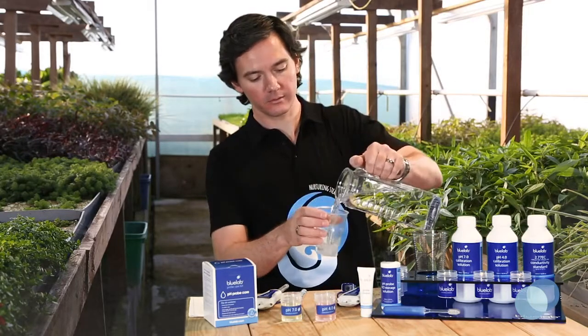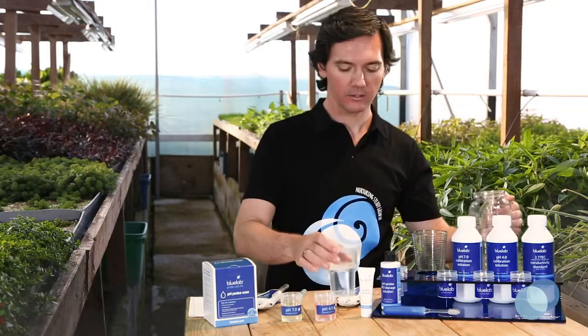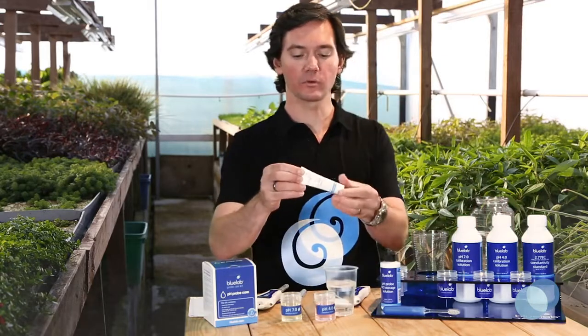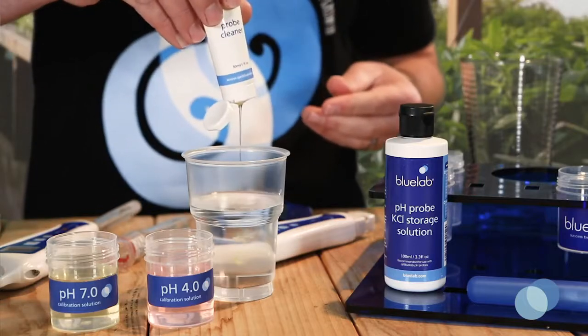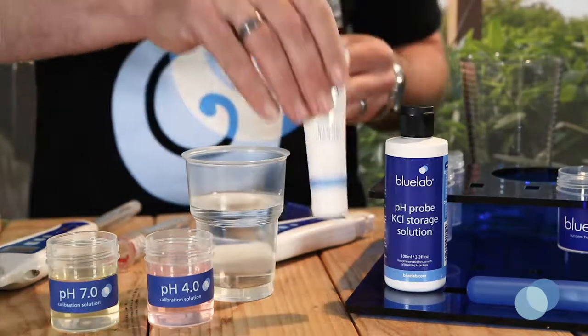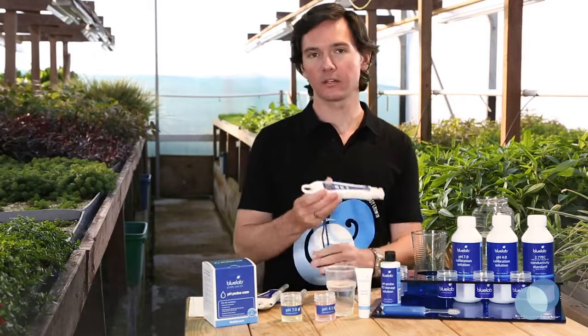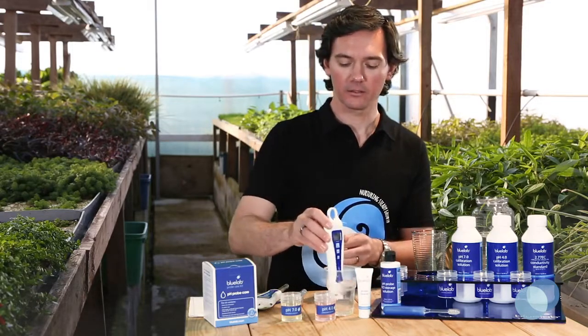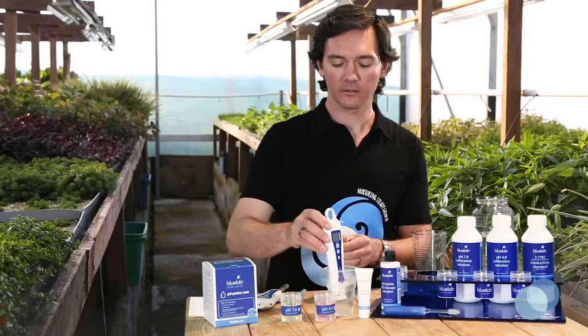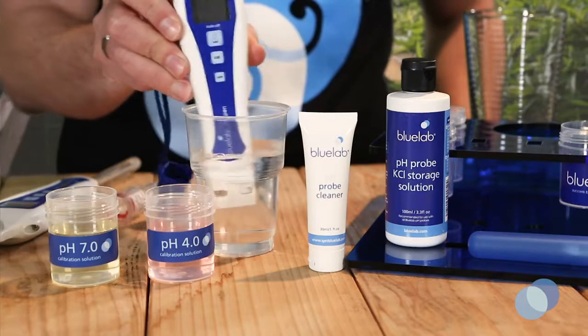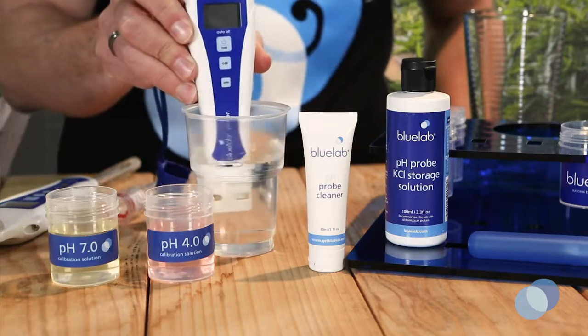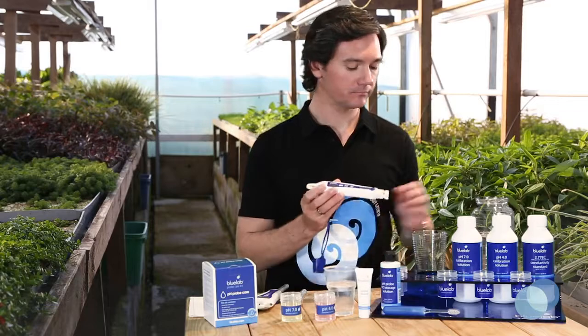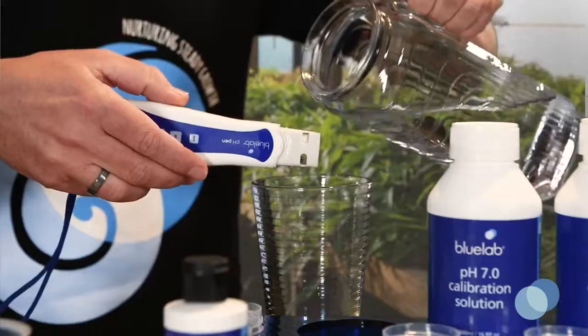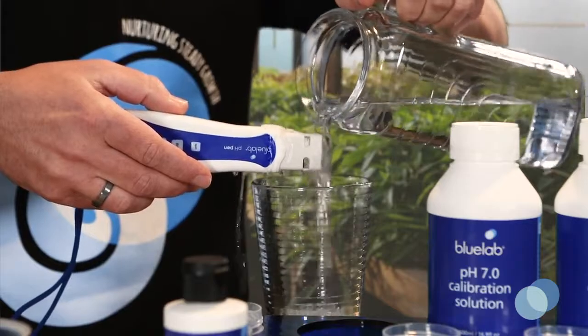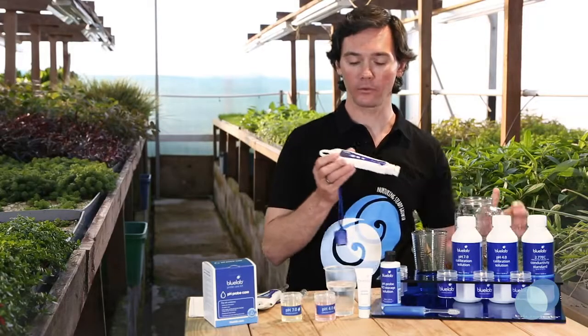Next, fill a plastic cleaning cup with clean tap water. Add a few drops of Bluelab pH probe cleaner to the water. For the standard pH pen, swirl the pen in the cleaning solution and take care not to knock the glass probe against the side of the container. That can cause damage to the probe. Take it out of the cleaning solution and give it a rinse with some fresh clean tap water. Make sure no traces of the cleaning solution remain on the probe.